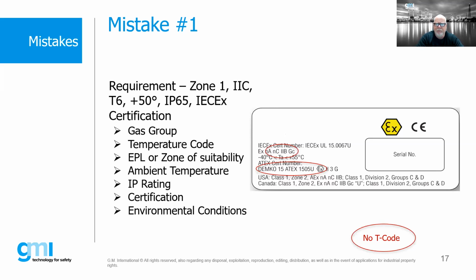So typically component certified products are usually things like switches, or some other device that's actually going to be installed as part of an overall system. Another giveaway is that usually component certified products will not have a T code. So if we don't see a T code and we see a U, that should immediately be a red flag and tell us that, hey, this product is a component. This cannot be installed. We have to be wary of that.